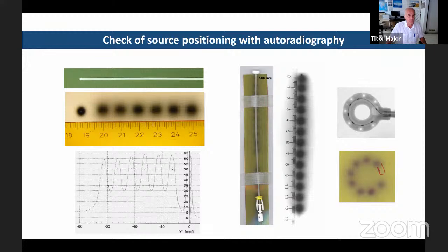So on the film, straight catheter were placed on the film, and at 1 centimeter separation, the source was stopped here. And on the film, we can see where the source stopped, and we can check the positions. We can measure how accurately the source was moved between the different positions. You can see the movement was 1 centimeter. The step size was 1 centimeter. In the middle, you can see the setup. This is the film and the catheter on the top of the film. And here again, you can see these black holes where the radiation source was stopped for a few seconds.